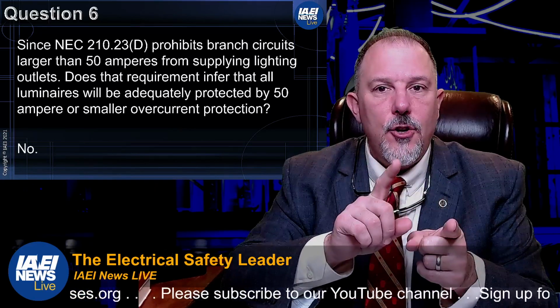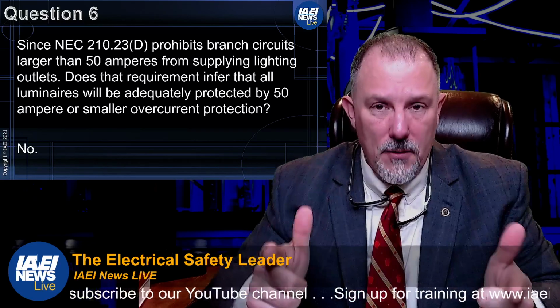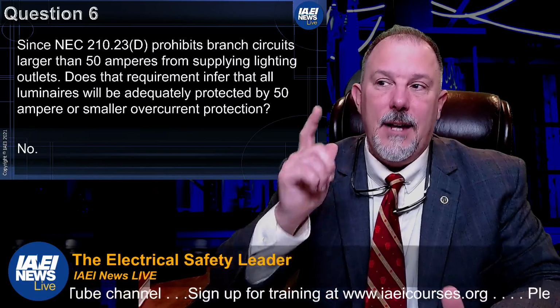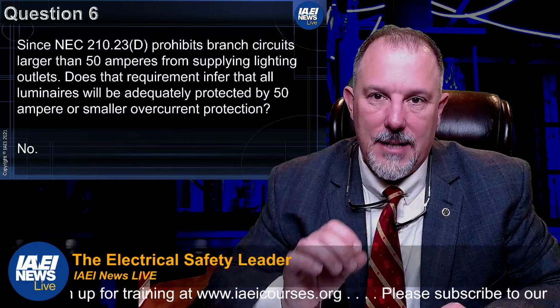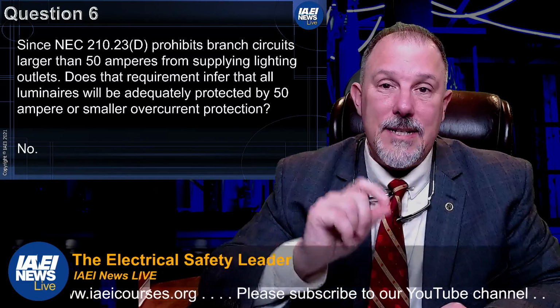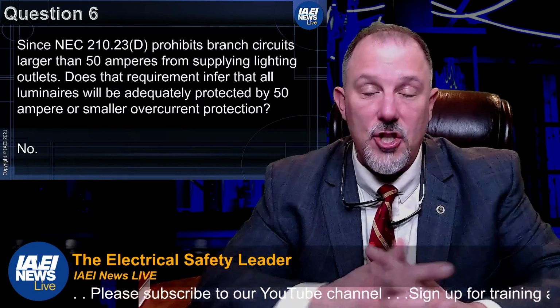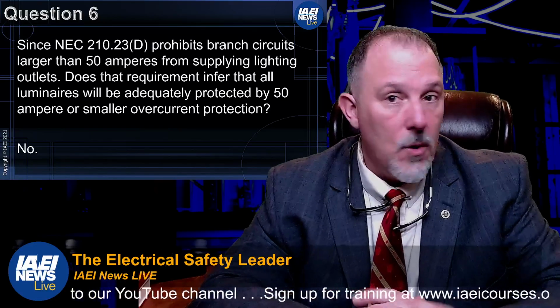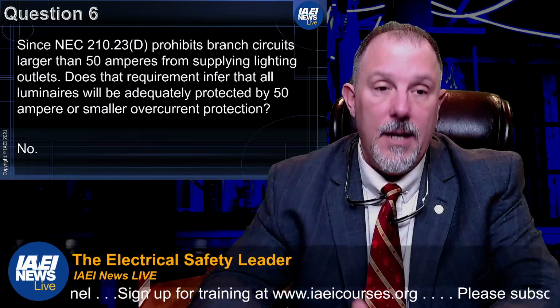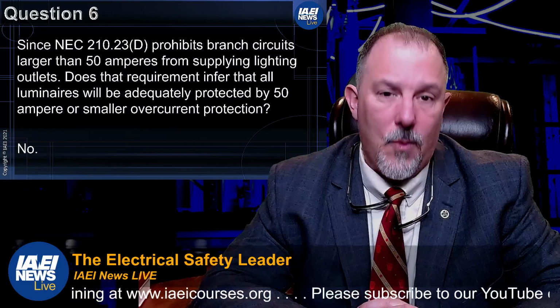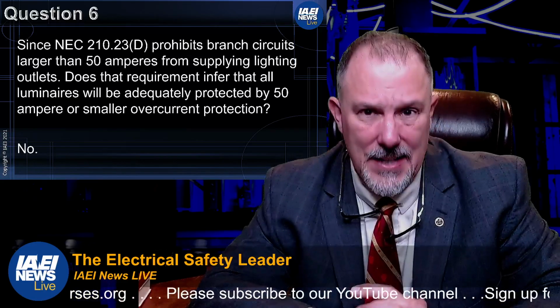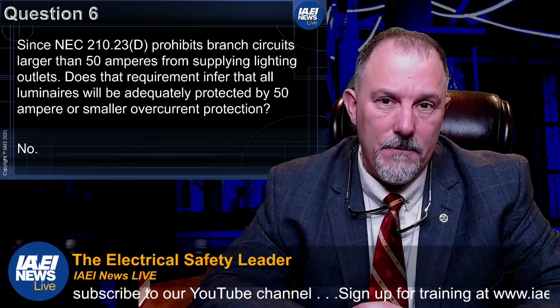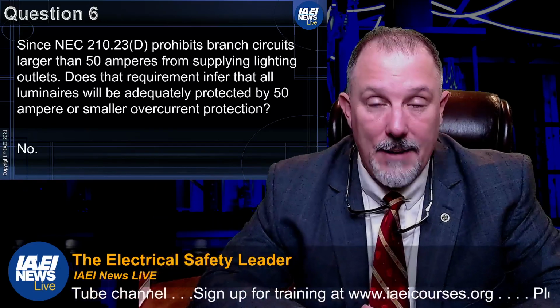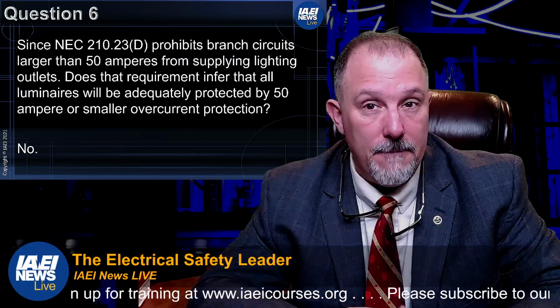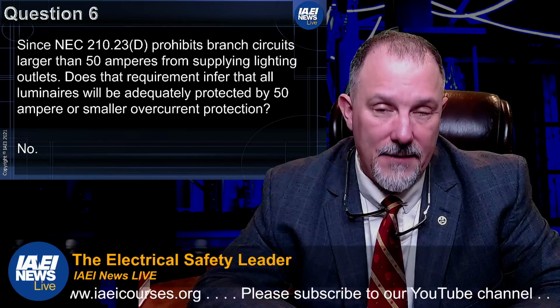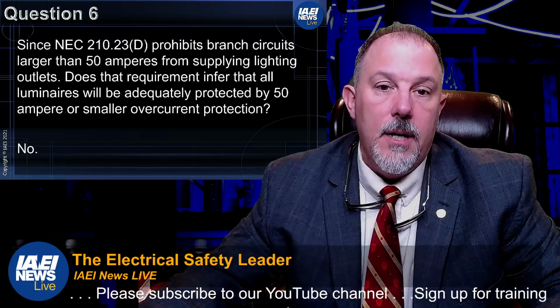And we understand that A, you purchase listed products, you install them per their listing based on 110.3(B), and those conductors, that fixture is considered to be protected, not because of the overcurrent protective device upstream. If you want additional GFCI protection, or if it's mandated based upon the location of that luminaire or that lighting outlet, then 210.8. Or you can elect to go above and beyond and provide GFCI protection. If it's in a room inside of a dwelling unit that requires AFCI protection, or a non-dwelling unit that requires AFCI protection, then you provide AFCI protection for that circuit. Or you can go above and beyond the bare minimum code requirements and provide that protection to help reduce the likelihood and severity. So you are controlling risk when you install things like AFCIs and GFCIs when they're not required by the code. All right, that was a long journey, wasn't it?